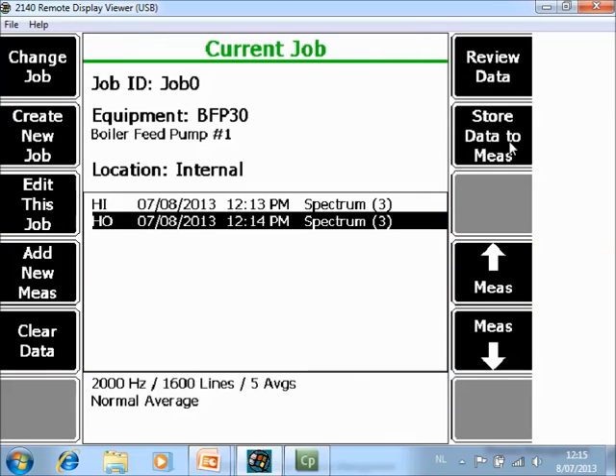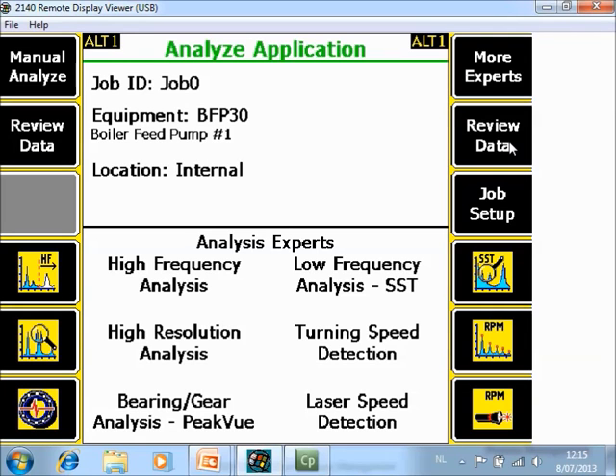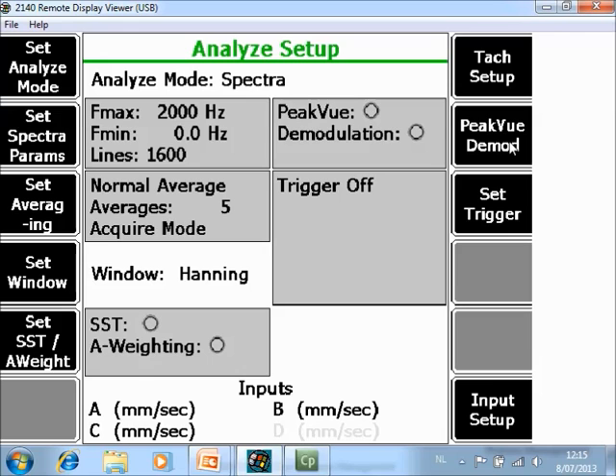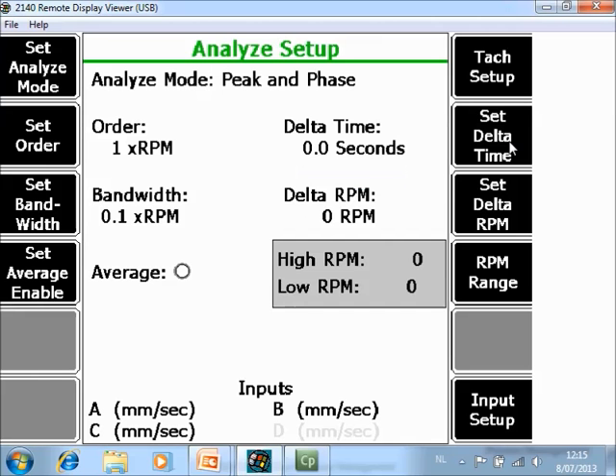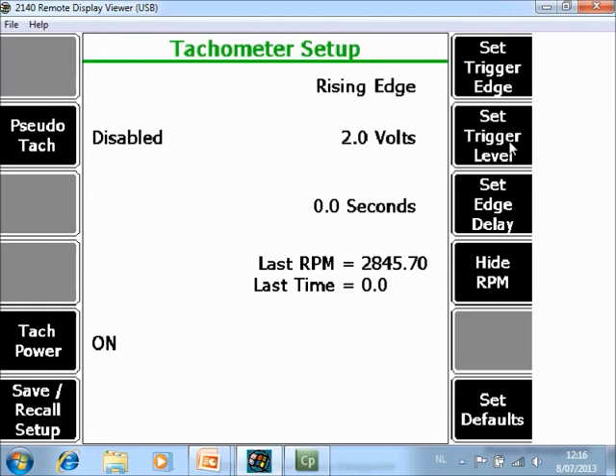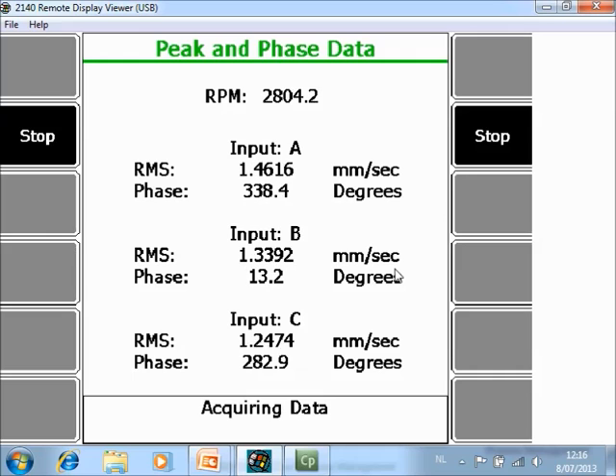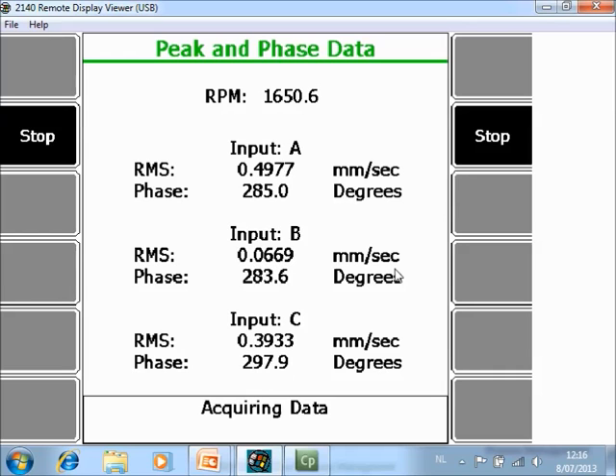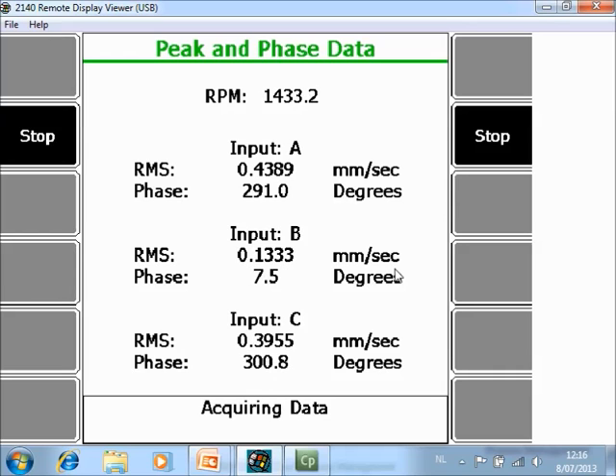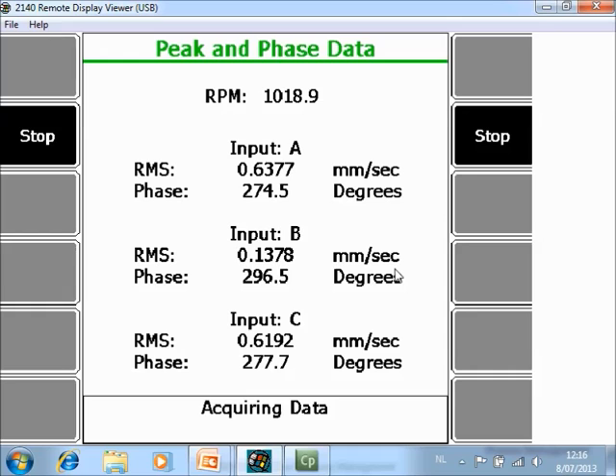Now I'm going to add a point, add measurement point, and I will collect now peak phase data, for example. So I go to manual analyze, set analyze mode, I go to peak phase. I check the tach setup. The tag is working because the speed is coming in. And I collect peak phase data during a run out. And when the speed is low, I stop data collection.